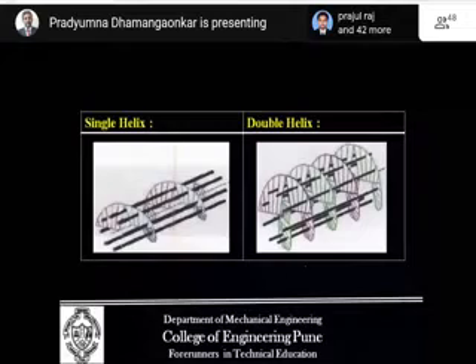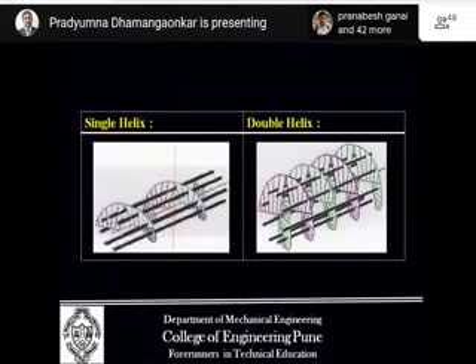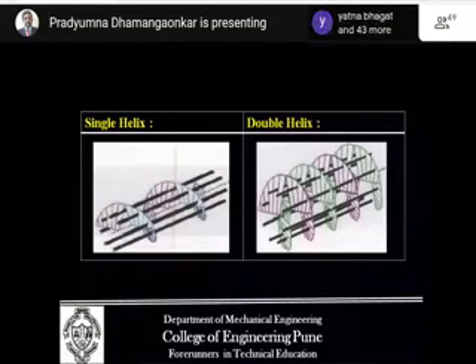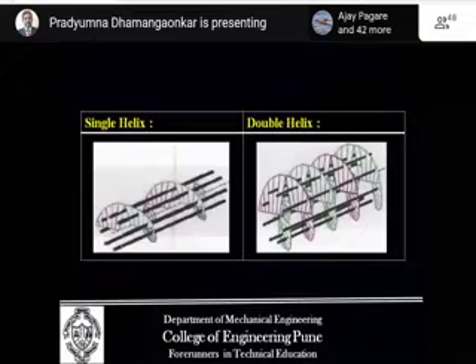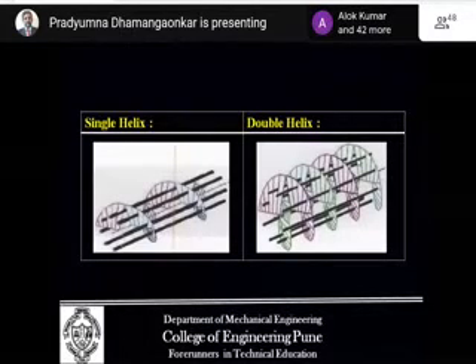There are two different types of helix available. First is the single helix. You will notice that a single helix goes around the tubes, and then there is a double helix. The violet color shows one helix, and the green color shows another helix. So these are the two helices. Due to this, there is a proper distribution of fluid along the tube surfaces, and thus no tube component will face a starvation of fluid. The entire surface gets in contact with the fluid and the heat transfer rate is improved.